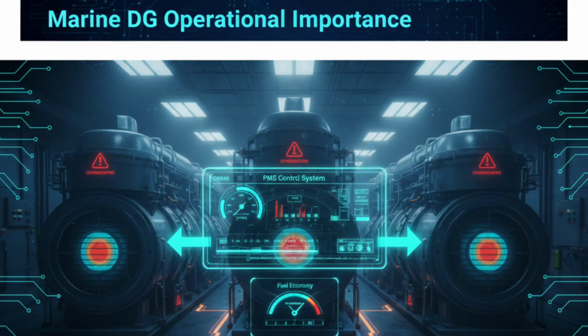Marine DG operational importance. Here we move into the ship's engine room, where multiple diesel generators operate in parallel and are supervised by a power management system, or PMS. Voltage regulation directly affects motors, pumps, compressors, and navigation equipment, while efficiency influences fuel consumption and exhaust emissions. Proper load sharing between generators prevents one machine from becoming overloaded while others run lightly loaded. The PMS automatically starts or stops generators to keep them within their optimum operating range.